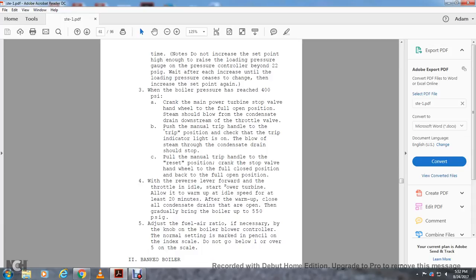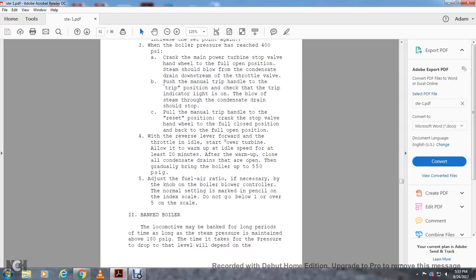With the reverse lever forward and throttle at idle, start the power turbine and allow it to warm up at idle for at least 20 minutes. After the warm-up, close all condensation drains that are open, and then gradually bring the boiler up to 550 PSI. Adjust the fuel-air ratio as necessary using the knob on the boiler blower controller — the normal setting is marked on the index scale. Do not go below 1 or over 5 on the scale.